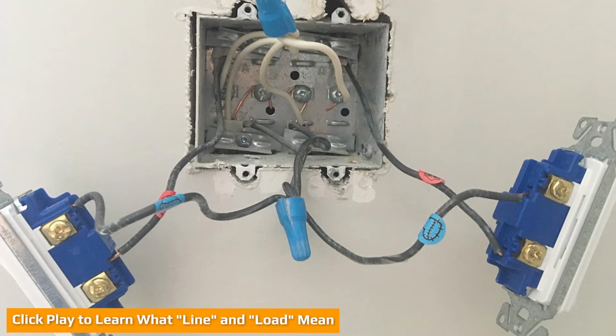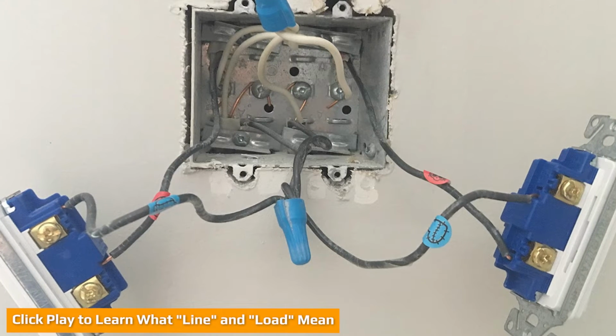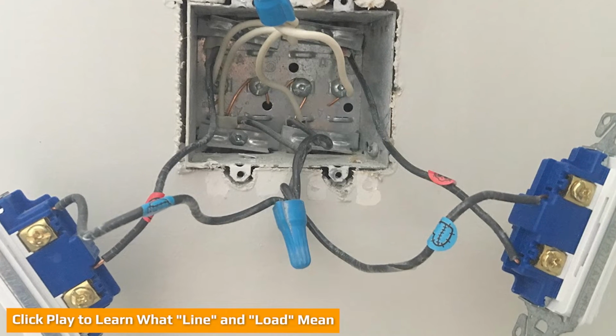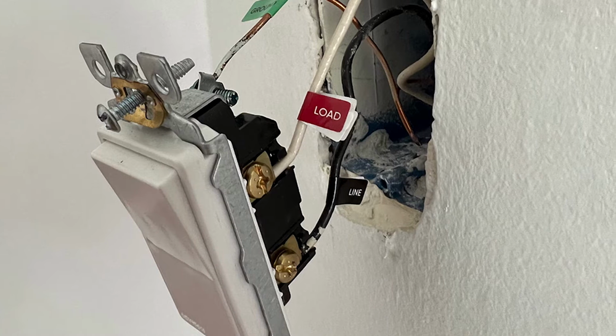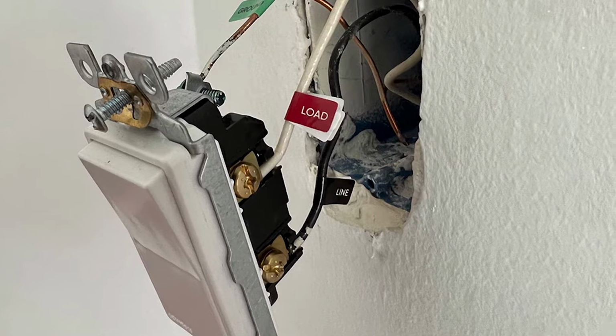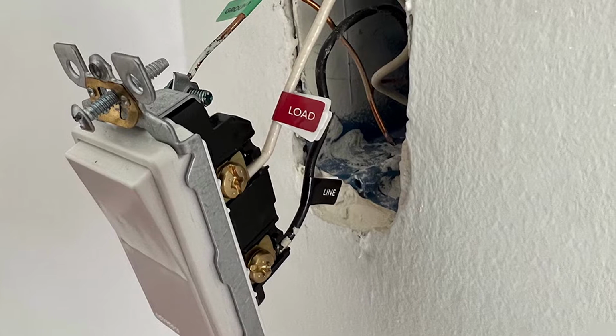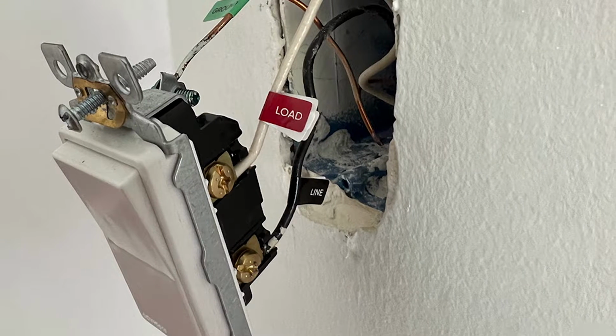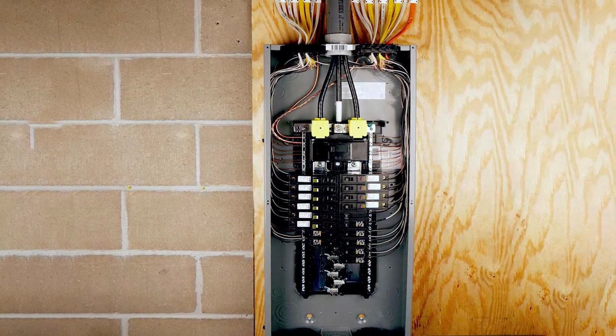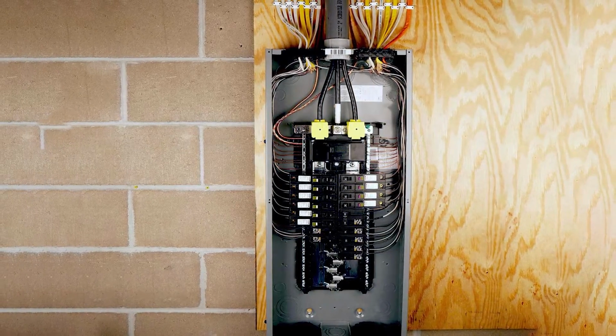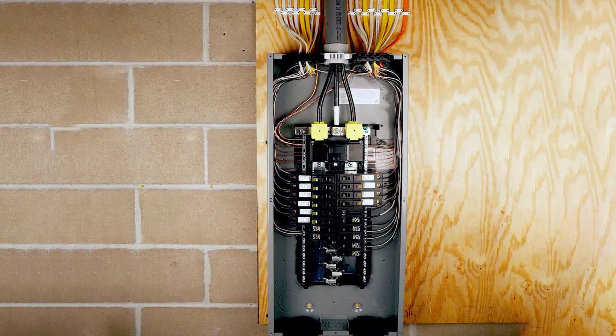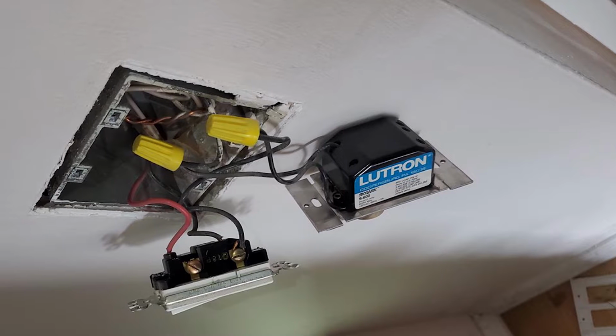The terms are used in the context of a single device and electrical box, so that the wires that deliver power into the box are described as the line wires, the upstream wires, or the incoming wires, while the wires passing onward to other devices are described as load, downstream, or outgoing wires. And these terms are relative to the location of the device in the circuit, since the load wire for one outlet becomes the line wire for the next receptacle downstream in the circuit.